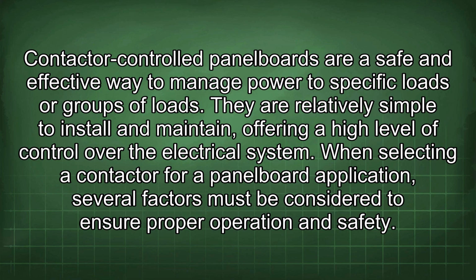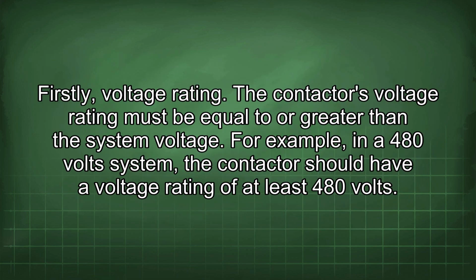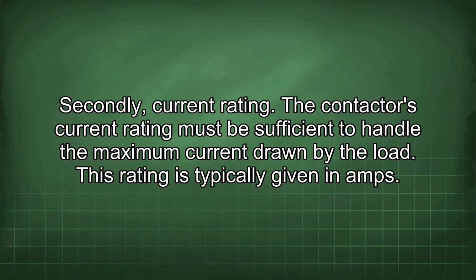When selecting a contactor for a panelboard application, several factors must be considered to ensure proper operation and safety. Firstly, voltage rating. The contactor's voltage rating must be equal to or greater than the system voltage. For example, in a 480-volt system, the contactor should have a voltage rating of at least 480 volts. Secondly, current rating. The contactor's current rating must be sufficient to handle the maximum current drawn by the load. This rating is typically given in amps.